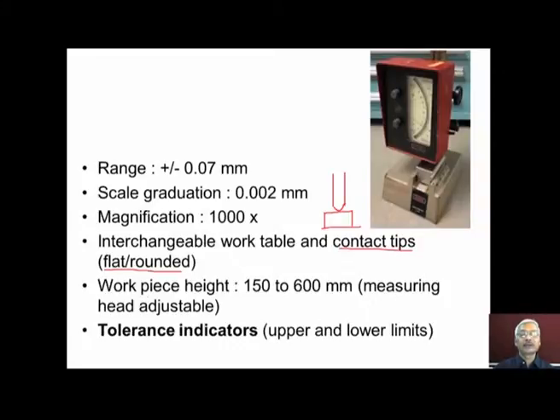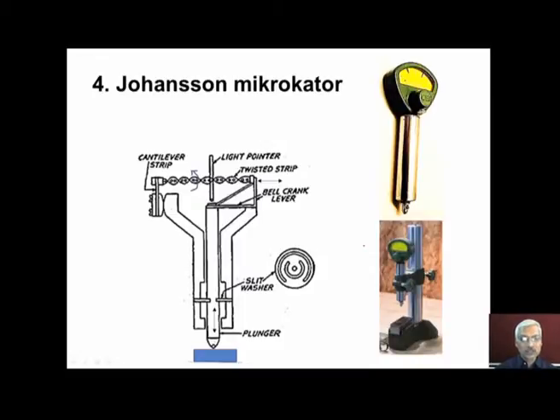The workpiece height that can be inserted between the plunger and the table surface varies from 150 millimeter up to 600 millimeter by adjusting the height of this measuring unit. And then we can also have the tolerance indicators, which will indicate the upper and lower limit of the workpiece. Now we'll move on to the discussion on Johansson microcator. The construction of the Johansson microcator is shown here.